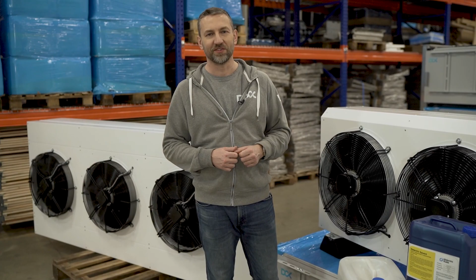You just need to calculate the 260 watts on the enclosure pump, which is also pretty strong. So these are the components which we use for the heat rejection for the single enclosure. The 40 kilowatt dry cooler is the most compact unit. It can be positioned literally anywhere. Customers install it on balconies, on roofs, wherever you like. Just make sure that you are leaving enough space: half a meter in the back, half a meter in the front. The more the better. Ideally on the north side of the building. And this is actually all you need to operate one single enclosure system.